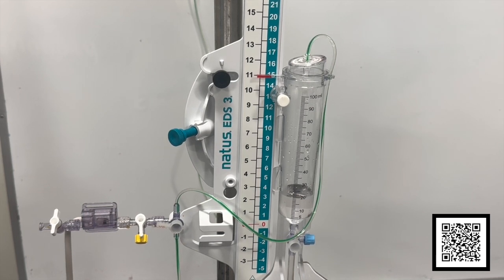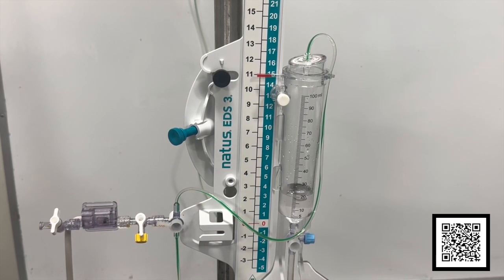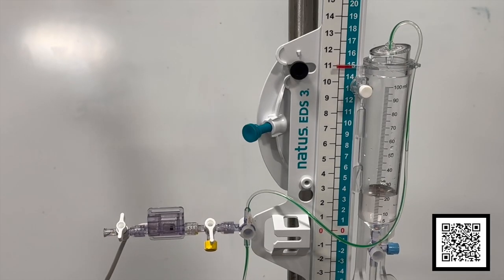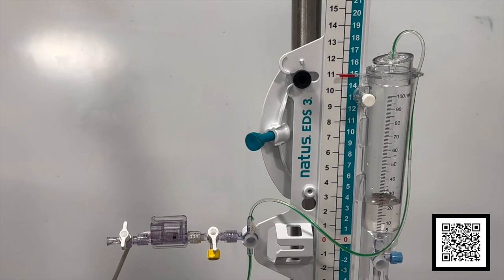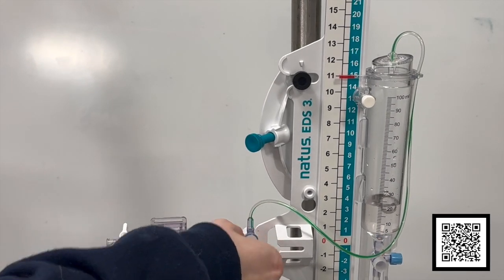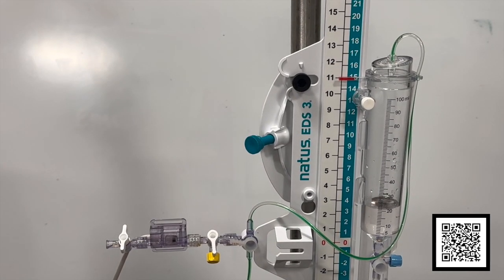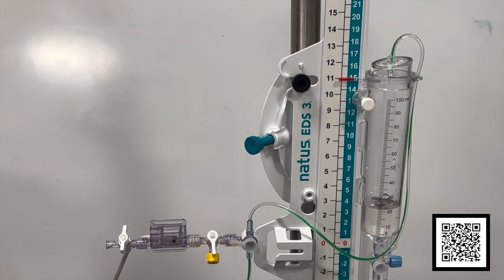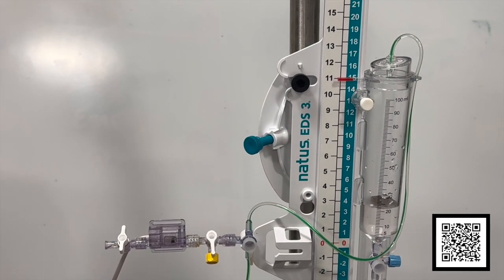The piece of the EVD that converts the pressure signal into an electrical signal displayed as a numerical value is called a transducer. The transducer allows clinicians to see intracranial pressure and make medical decisions. The process of calibrating an EVD transducer is called zeroing. There are two methods to zero an EVD.